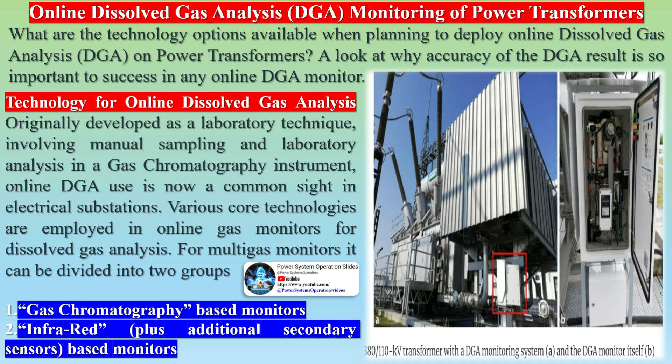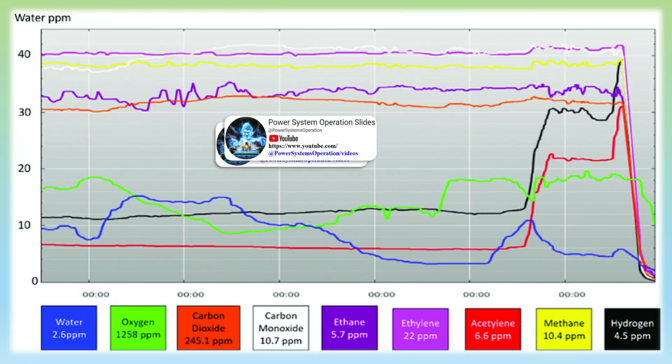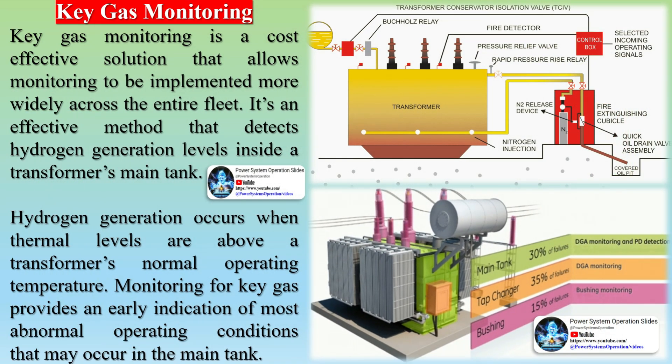For multi-gas monitors, technologies can be divided into two groups: gas chromatography-based monitors and infrared plus additional secondary sensors-based monitors. Key gas monitoring is a cost-effective solution that allows monitoring to be implemented more widely across the entire fleet. It is an effective method that detects hydrogen generation levels inside a transformer's main tank, and monitoring for key gas provides an early indication of most abnormal operating conditions.